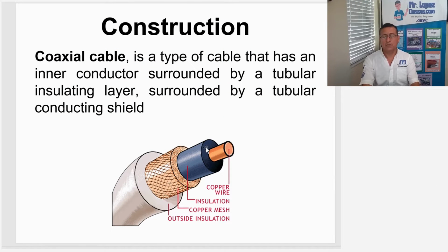The shield. This is the insulation, normally a plastic, and this is the center conductor. The center conductor comes in two shapes, solid or stranded. Normally in marine applications stranded is recommended because we need more flexibility, exactly the same as in our previous book with the marine cables.